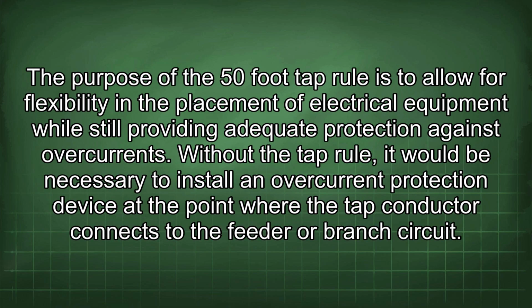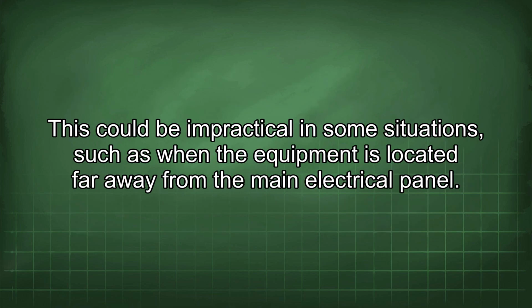The purpose of the 50-foot tap rule is to allow for flexibility in the placement of electrical equipment while still providing adequate protection against overcurrents. Without the tap rule, it would be necessary to install an overcurrent protection device at the point where the tap conductor connects to the feeder or branch circuit. This could be impractical in some situations, such as when the equipment is located far away from the main electrical panel.